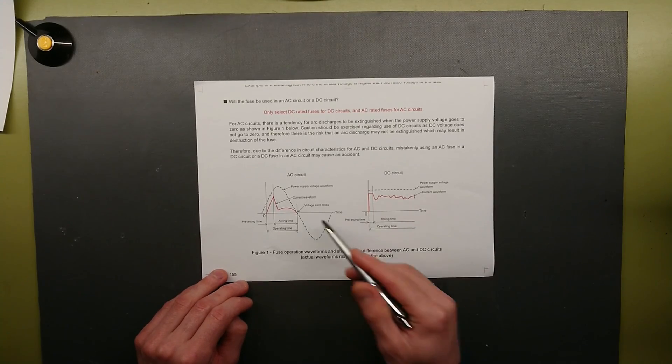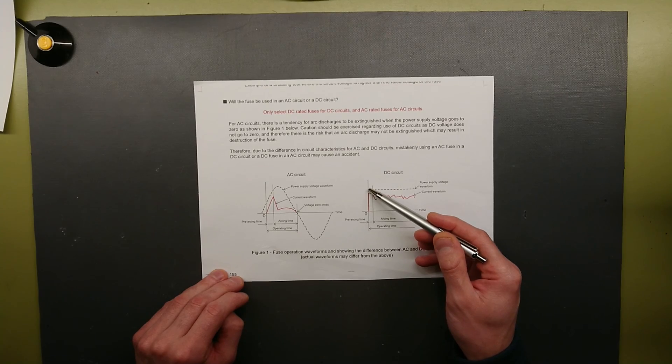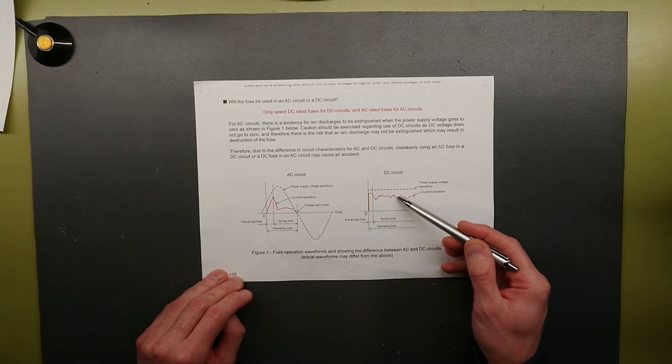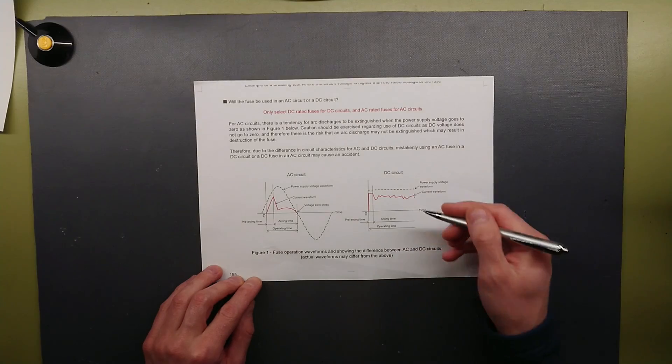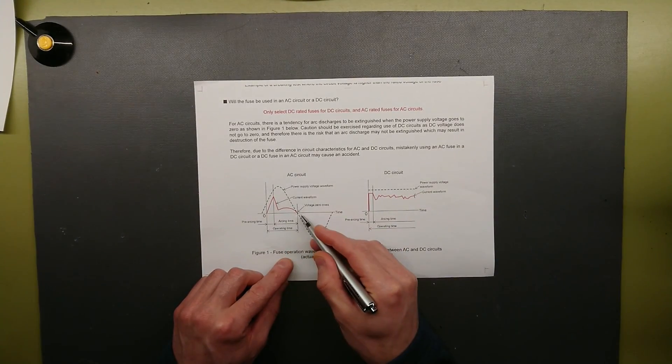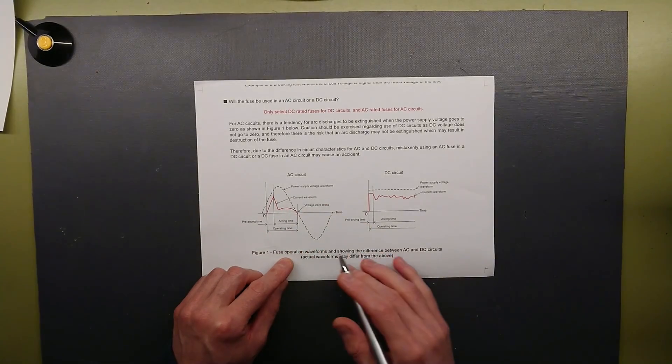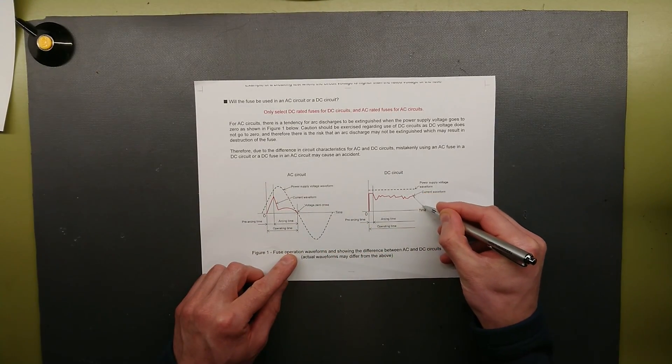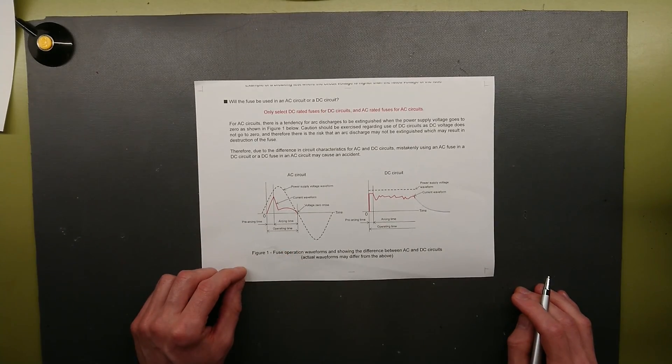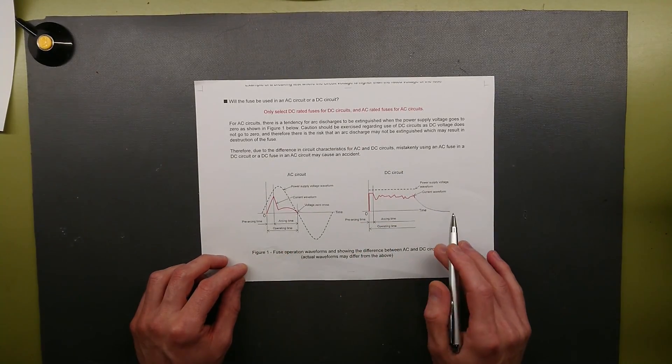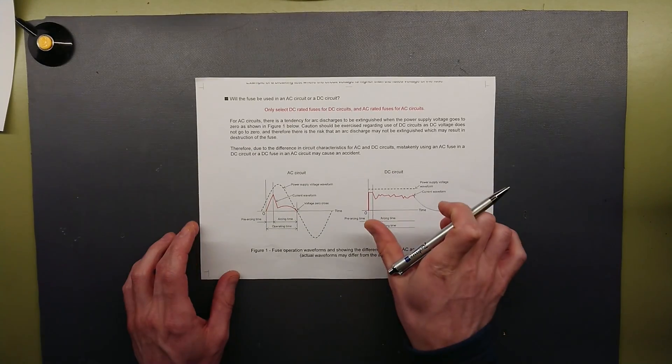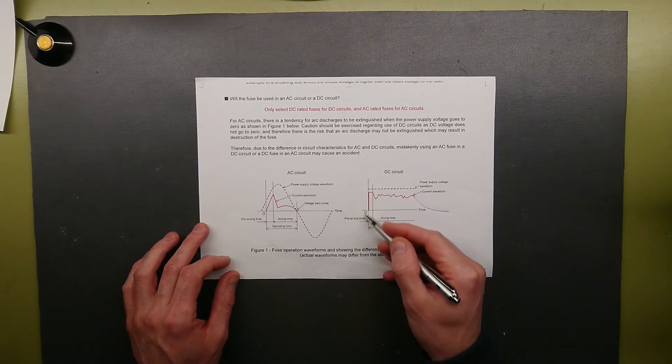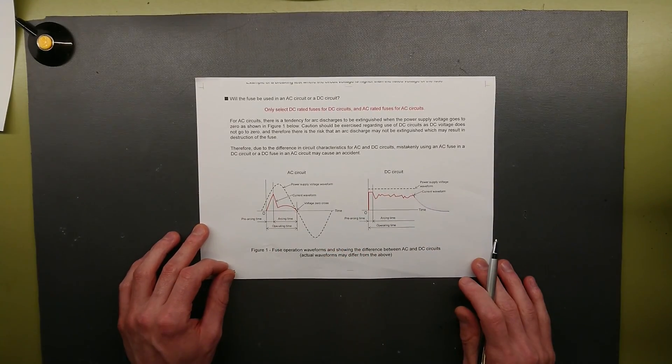The fault current goes up on a fast acting link and it will diminish and go to zero as the voltage goes to zero. But when we look at the fault current at a DC circuit it will jump up fast, but then it will be very abrupt while arcing. While it is finally arcing out it will not diminish according to the AC circuit voltage. It will more have an RC circuit decline. That is why the arcing and melting time for a DC fuse is much longer. There is so much more energy or square area under the graph compared to the AC circuit.